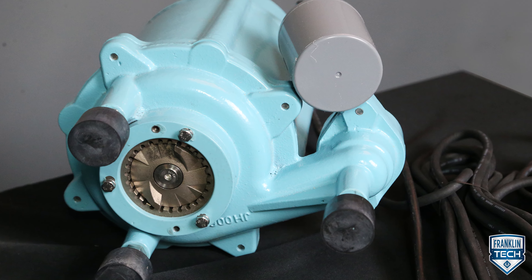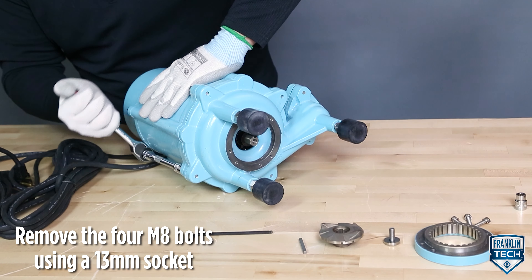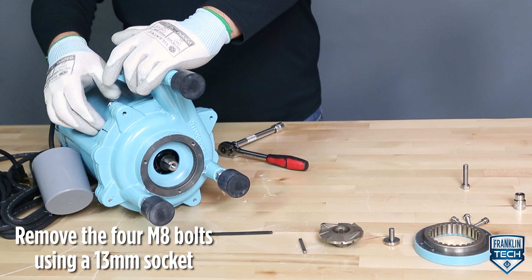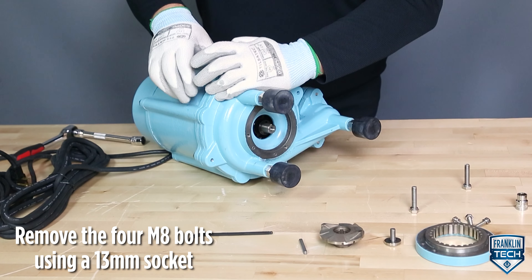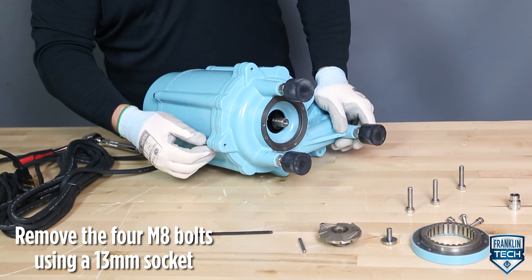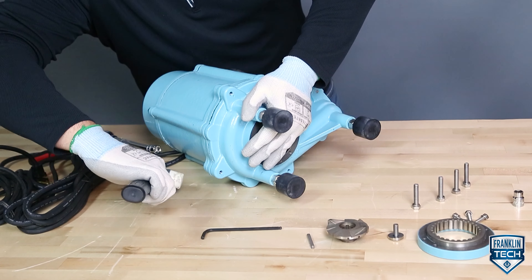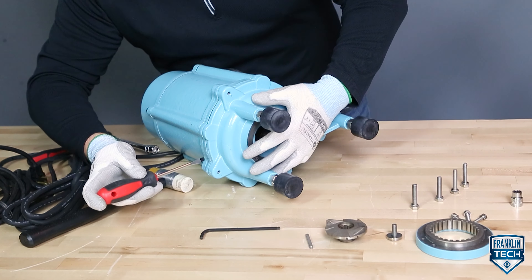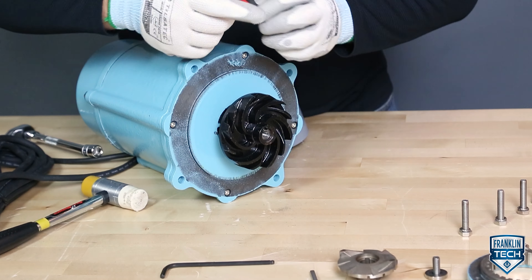To disassemble the volute, remove the 4 M8 bolts that hold the volute to the seal plate using a 13 mm socket. If needed, lightly tap the volute with a rubber hammer to separate it from the seal plate. As a secondary option, use a screwdriver to gently break the volute free. Using two screwdrivers or a gear puller, pull the impeller off of the motor shaft.